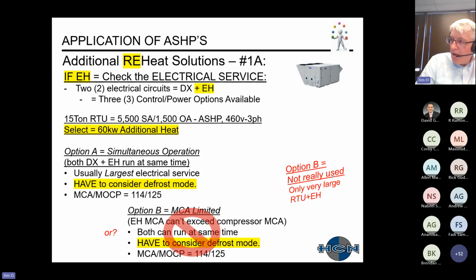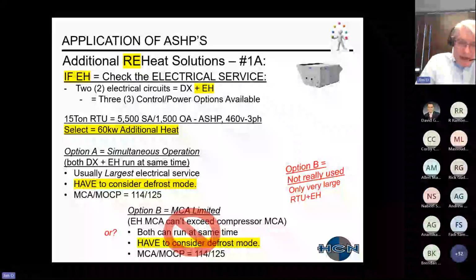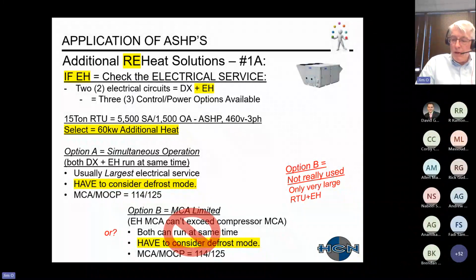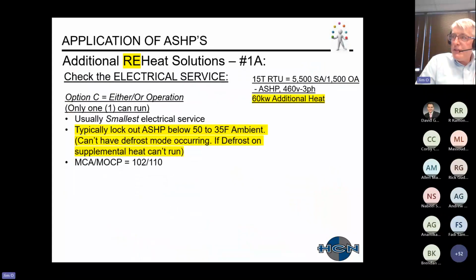This is only done on very large rooftop units with electric heat, because, say you have 208 volts with 60 or 70 tons, you end up with a large electrical service. The other option, I'll call it option C, is an either-or operation. You can either run the refrigeration or the electric heat. You can't run them both at the same time. This has the smallest electrical service requirement, obviously, because you're not running both items.